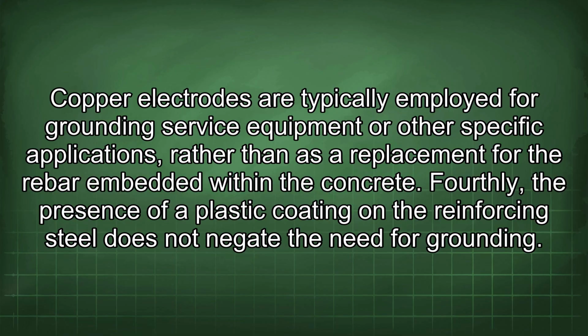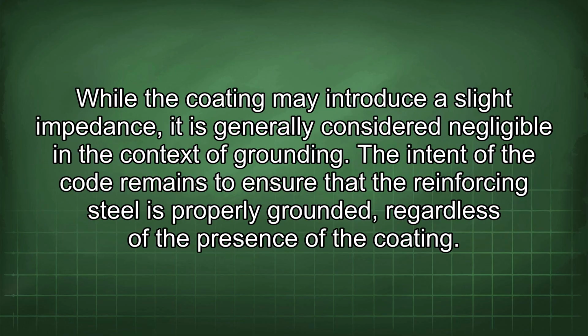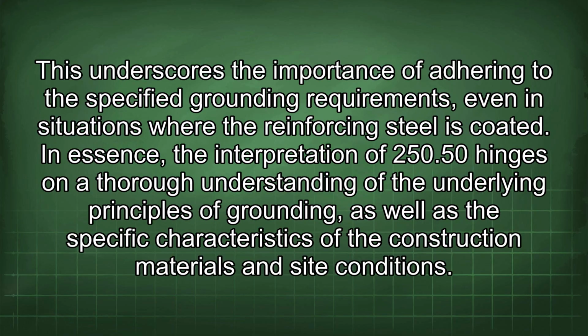Fourthly, the presence of a plastic coating on the reinforcing steel does not negate the need for grounding. While the coating may introduce a slight impedance, it is generally considered negligible in the context of grounding. The intent of the code remains to ensure that the reinforcing steel is properly grounded, regardless of the presence of the coating. This underscores the importance of adhering to the specified grounding requirements, even in situations where the reinforcing steel is coated.